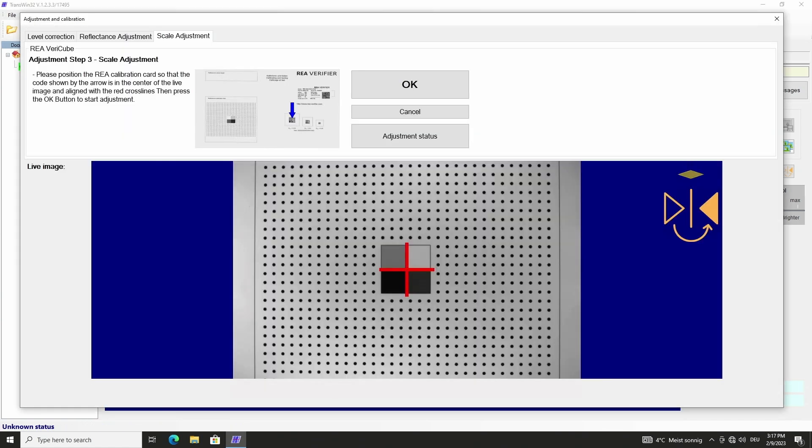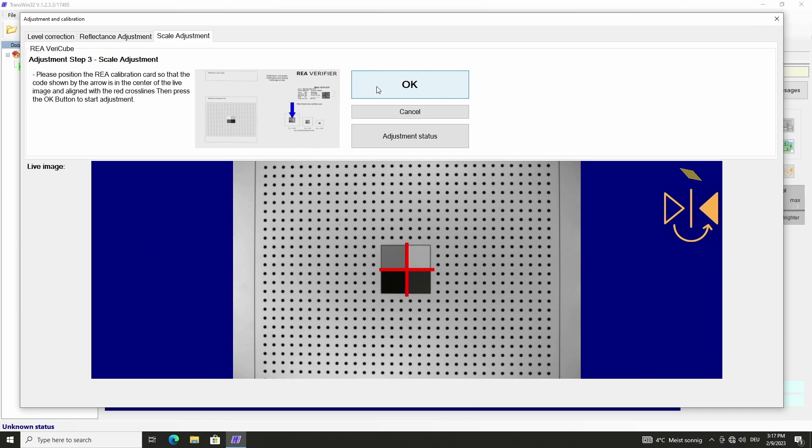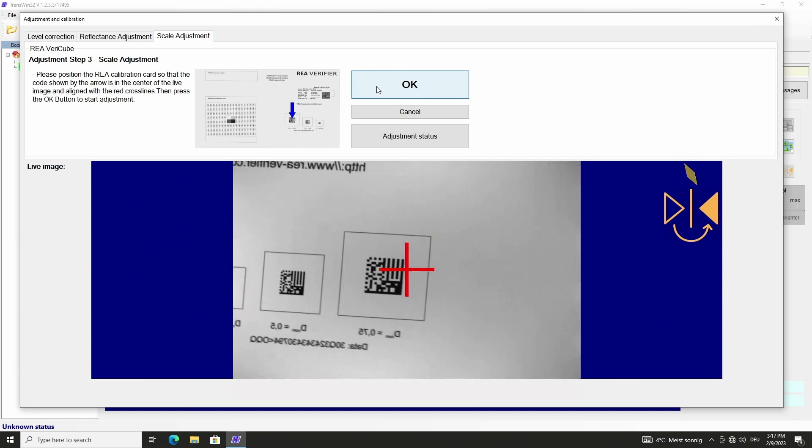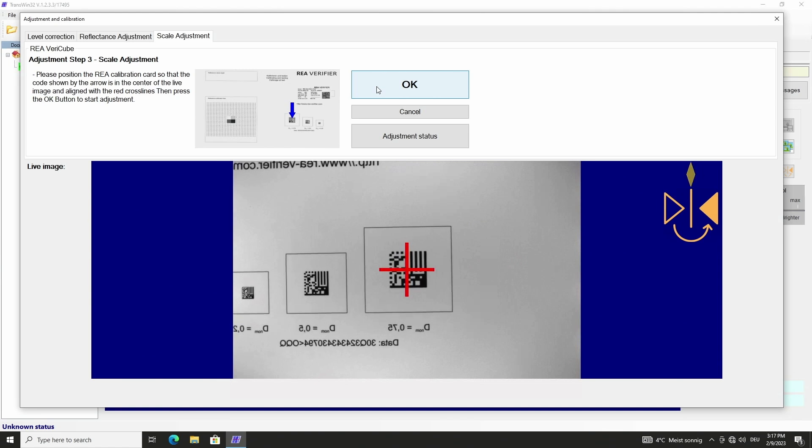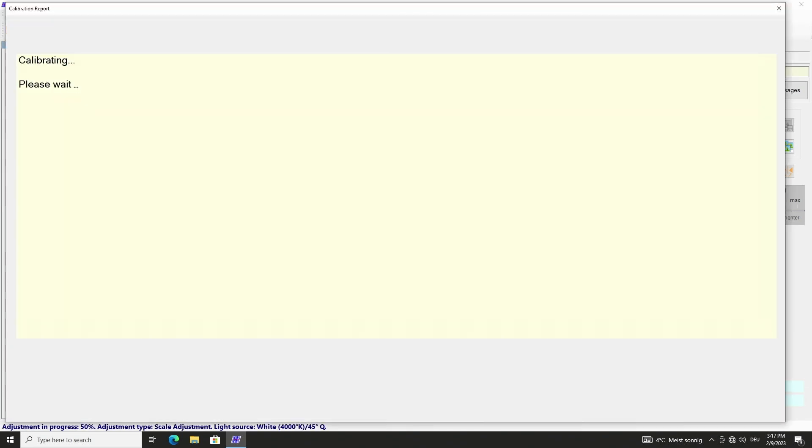The third step is the scale adjustment with the data matrix symbol that is marked on the picture in the software. In our case the symbol with DNOM 0.75 must be used for our camera module with focal length 8 mm. We move it in the area of the crosshairs parallel to the axis and add the black plate on top of the calibration card. We start scale adjustment with OK.